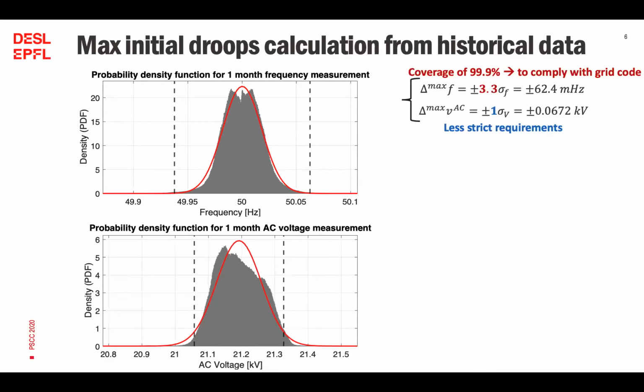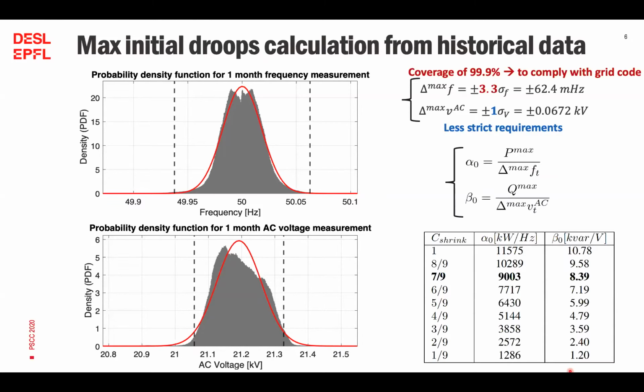On the other hand, less strict requirements regulate the quality of the supply for the local voltage control. In this case, we were a bit more relaxed in the choice of these factors, so we decided to pick one which was guaranteeing a coverage of about 70% of the cases. So in this way, we could finally calculate the initial droop values, alpha and beta, for the primary frequency control and the local voltage control cases.